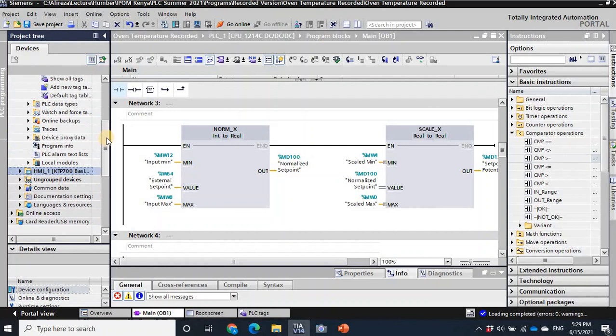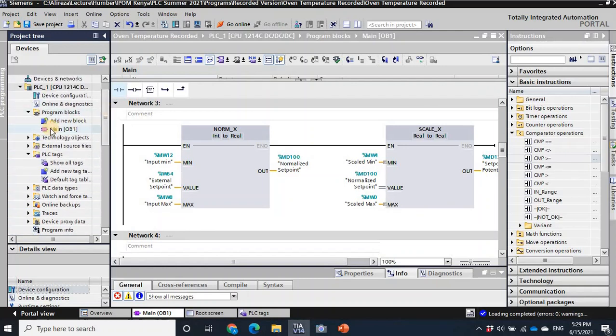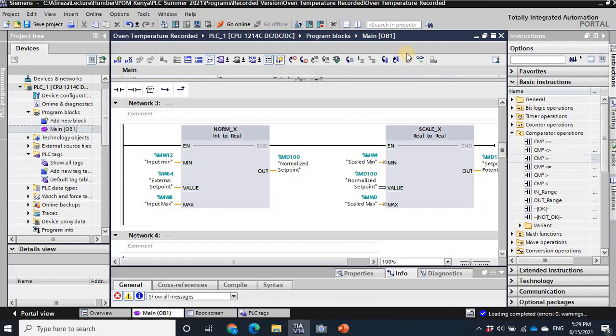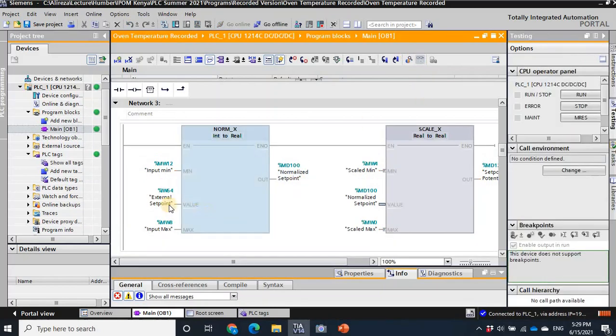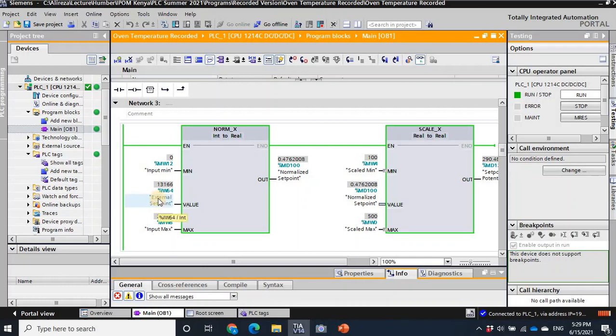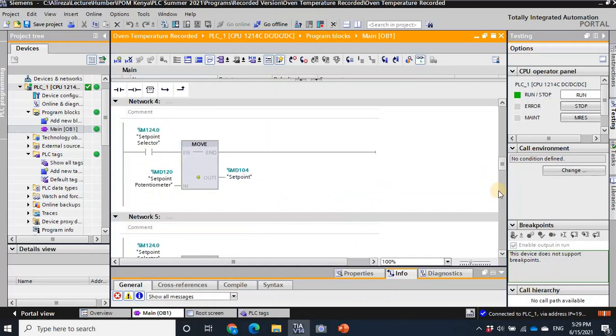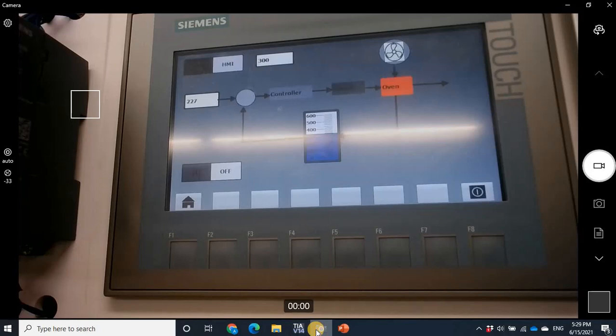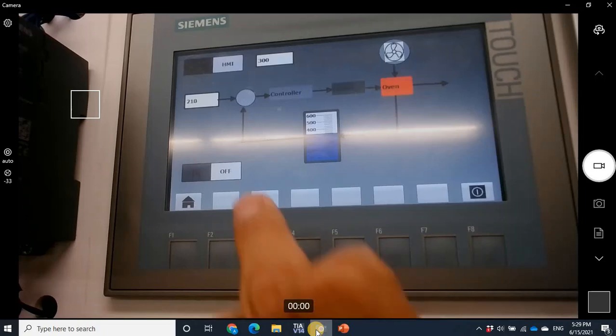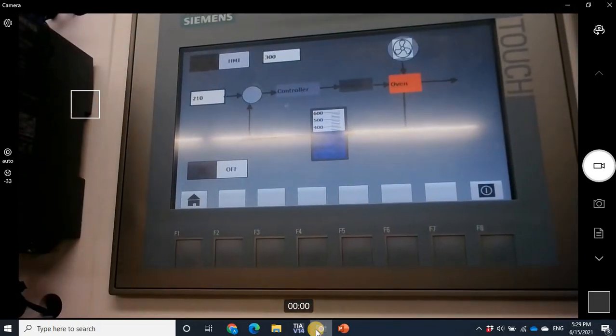Let's monitor now. I change the potentiometer for the set point — the normalized set point changes, and the set point itself changes. Looking at the HMI, you can see the set point changes. This confirms the set point is now updating correctly.